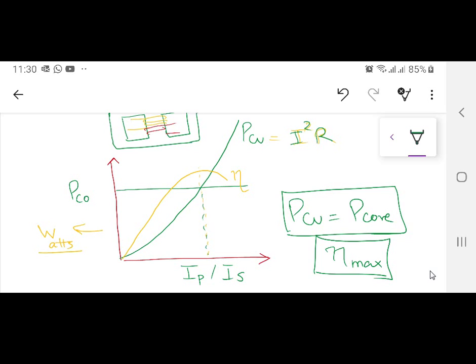Now let's talk about the transformer that is outside the department. It's a distribution transformer. It's taking that 11 kV, giving you 400 volt 3 phase, or line to neutral 220 or 230 volts. Now since we are only working in the morning time, our class will be from 8 to 4, this is the peak time.